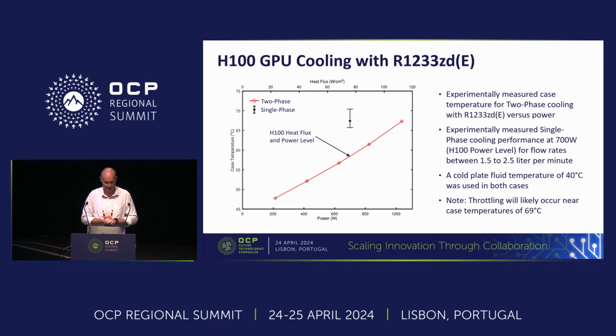You can see we point that out there. So at a 40-degree C inlet to the cold plate, our case temperature was roughly 57 degrees C, well below the throttle point, which is expected to be around 69 degrees in terms of case temperature. The junction temperature is closer to 87 degrees C.